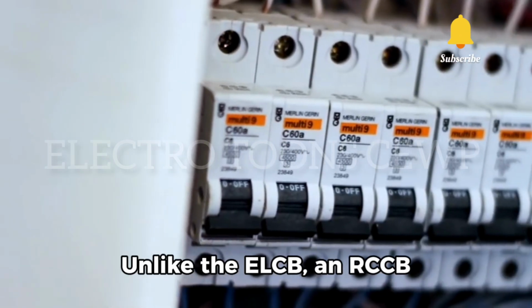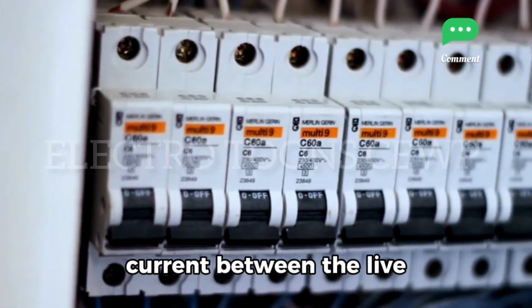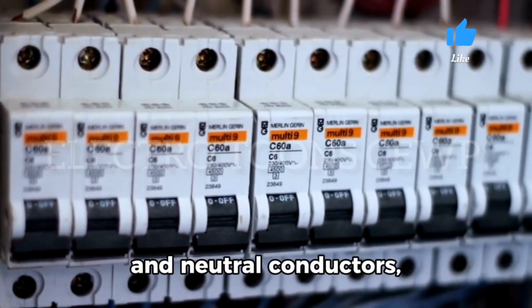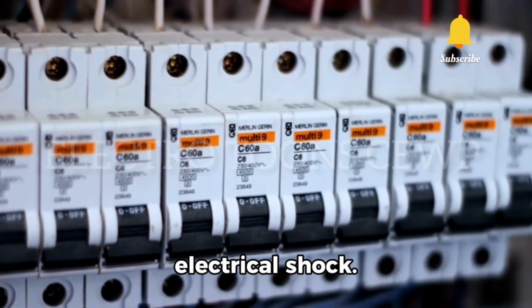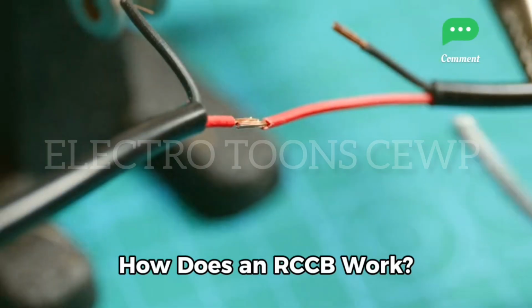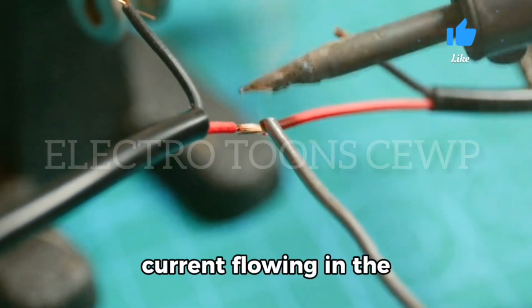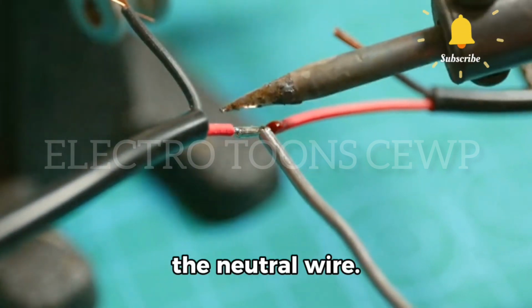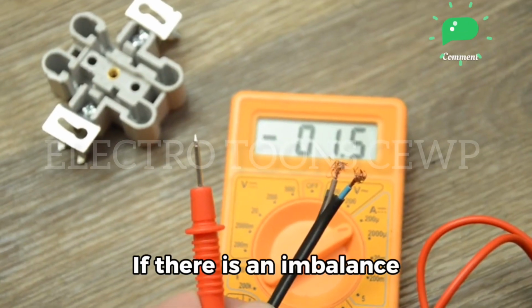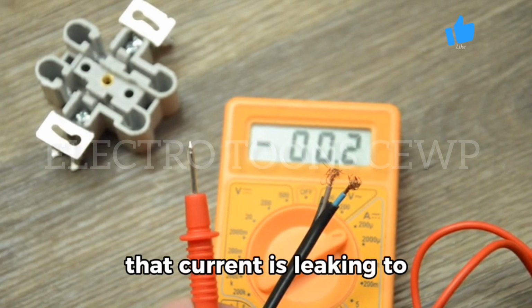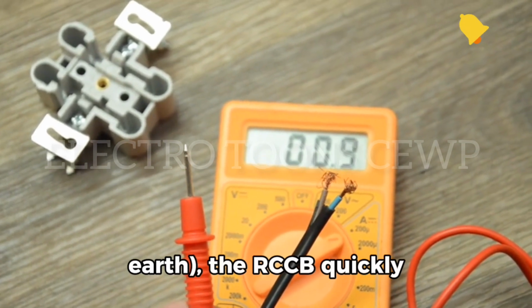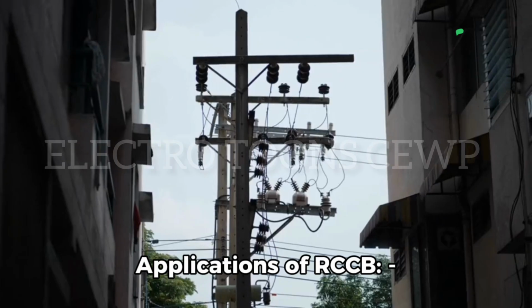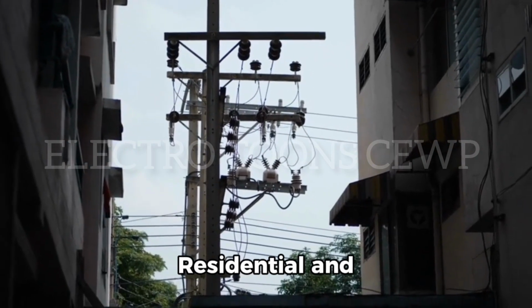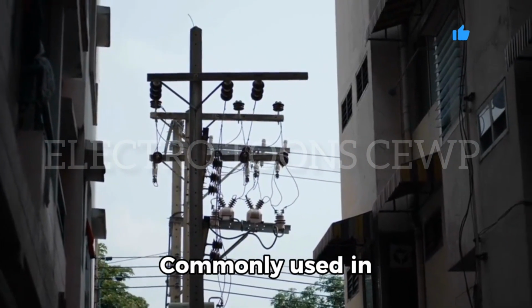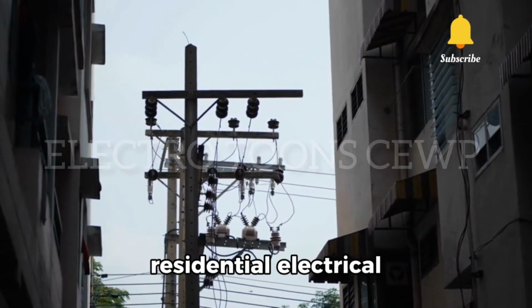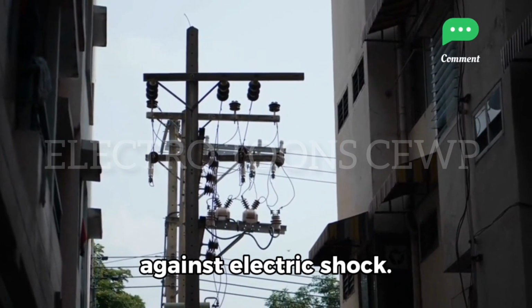Unlike the ELCB, an RCCB detects the difference in current between the live and neutral conductors, which helps in preventing electrical shock. How does an RCCB work? RCCBs compare the current flowing in the live wire to that in the neutral wire. If there is an imbalance between the two, suggesting that current is leaking to earth, the RCCB quickly disconnects the circuit. Applications of RCCB: residential and commercial buildings, commonly used in residential electrical systems to protect against electric shock.